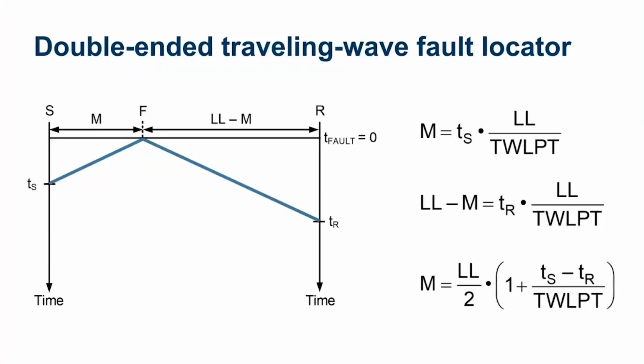So the double-ended traveling wave fault locator method requires communications between both relays. The relay at terminal S is going to have a high-speed fiber optic channel that's connected to the relay at terminal R. So we're going to exchange data between both relays, the arrival times, and we're going to be able to accurately locate the fault on this line.